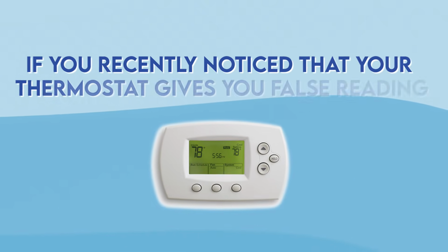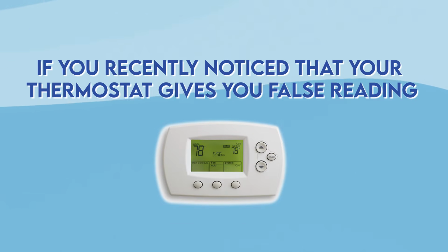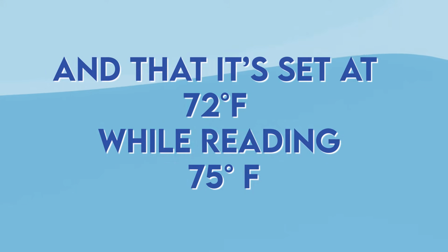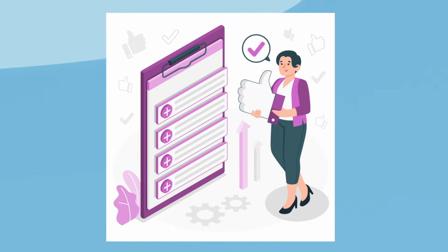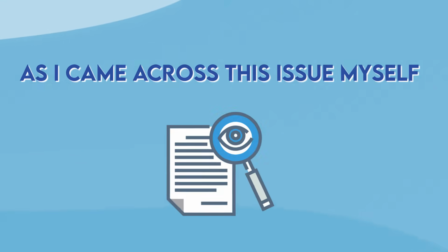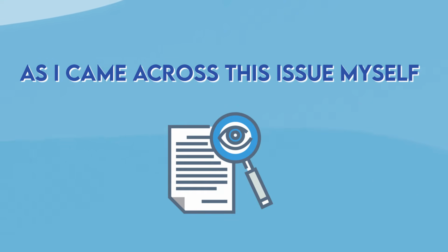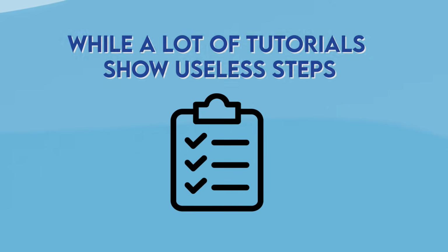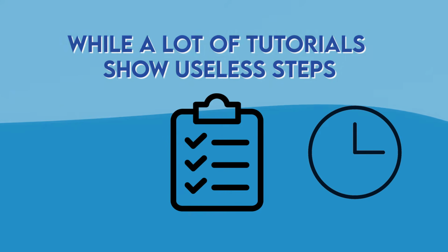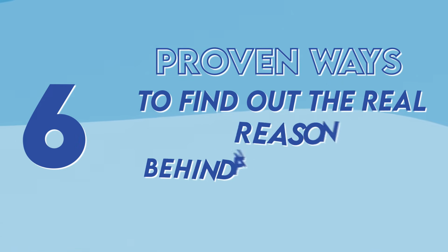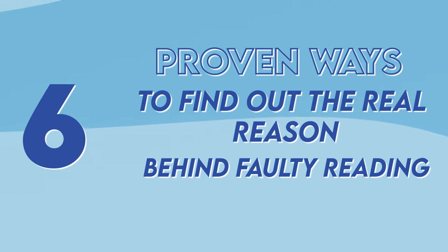If you recently noticed that your thermostat gives you false readings, and that it's set at 72 degrees while reading 75, there could be a ton of different reasons. As I came across this issue myself, I've done a lot of research to find out the real cause of it. While a lot of tutorials show useless steps that might waste your time, I have prepared 6 proven ways to find out the real reason behind faulty readings. So let's get into it.